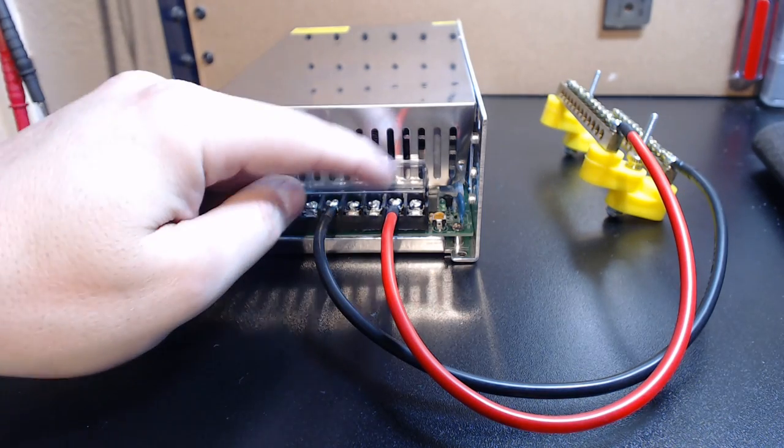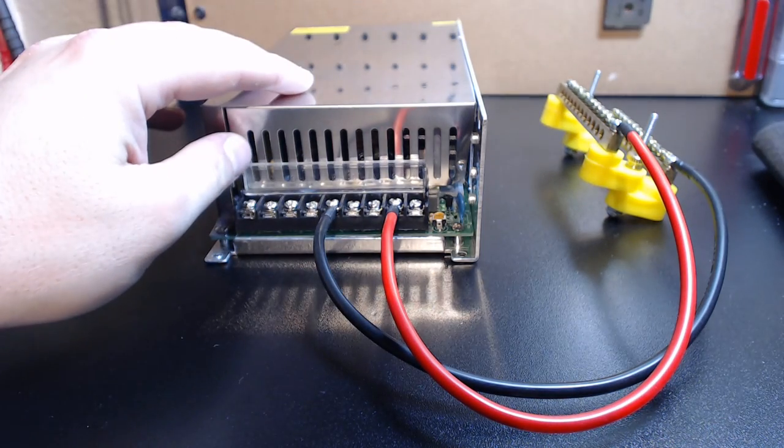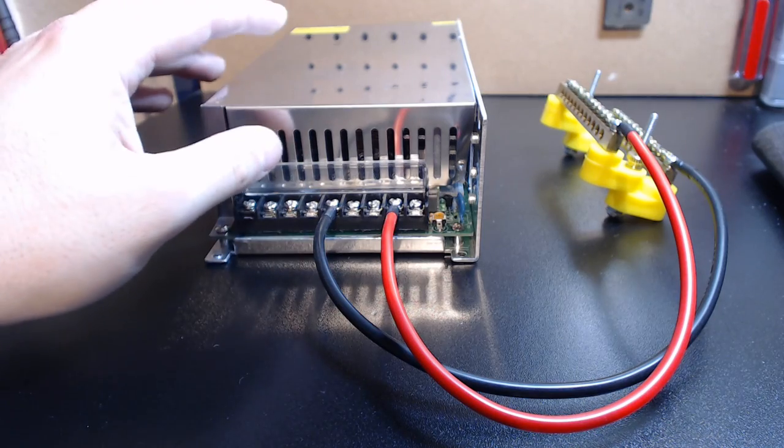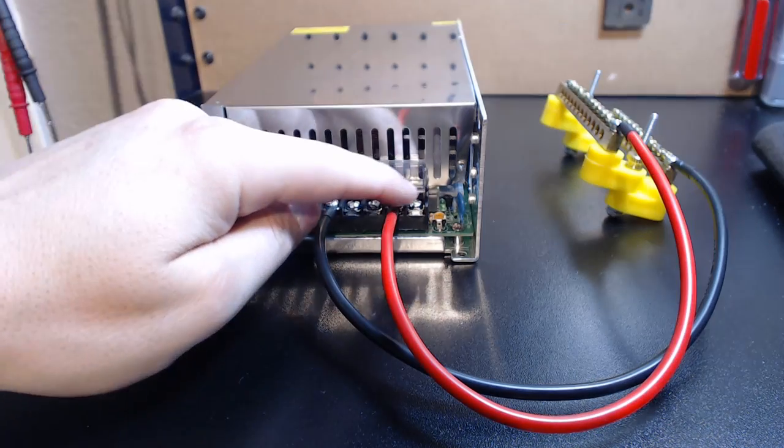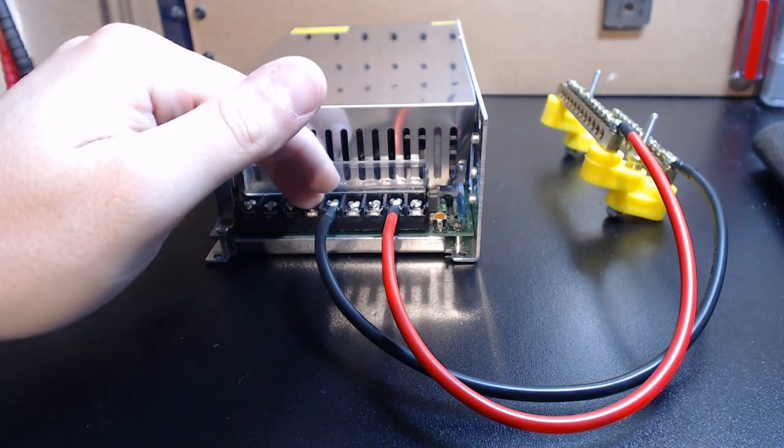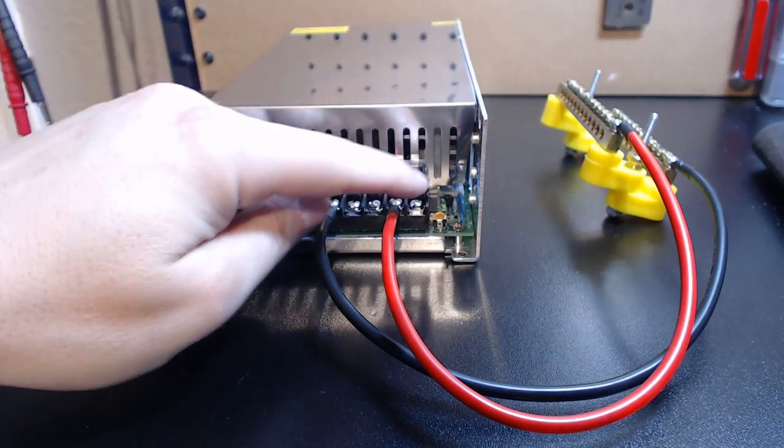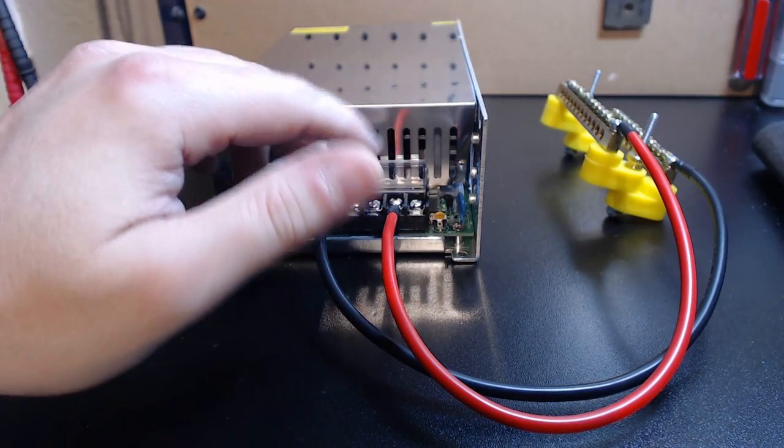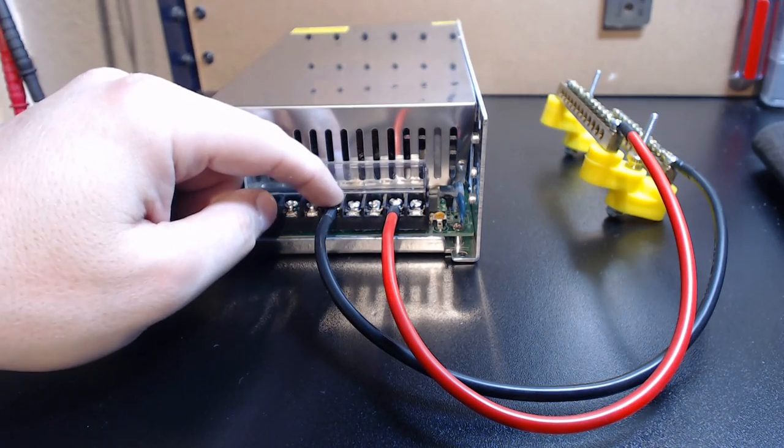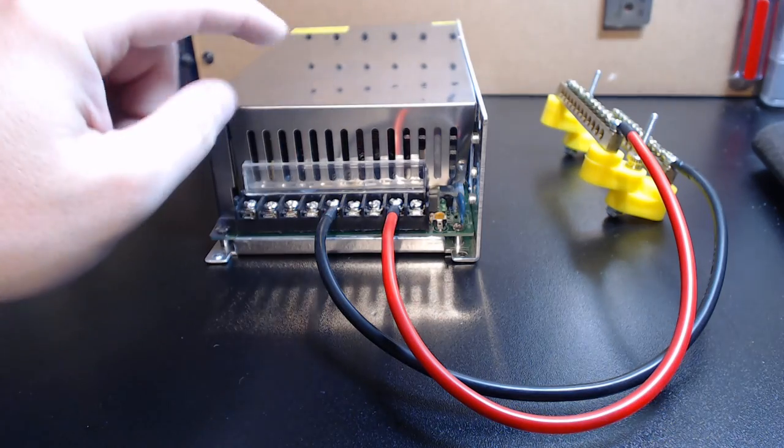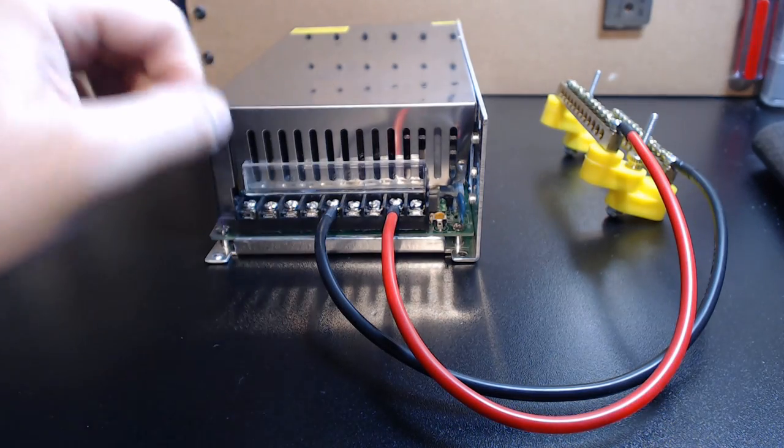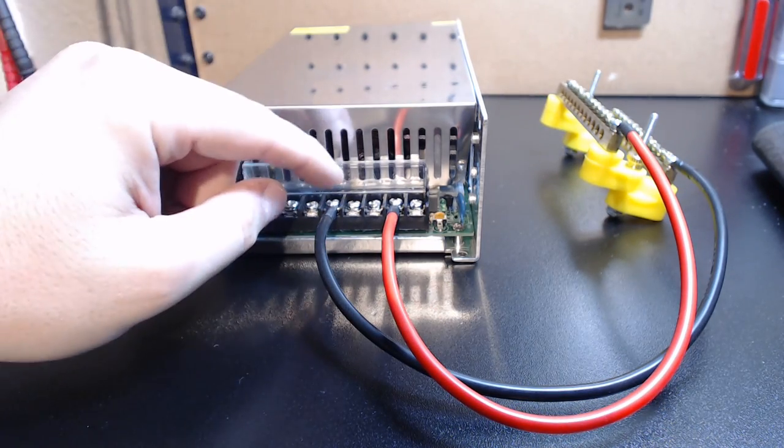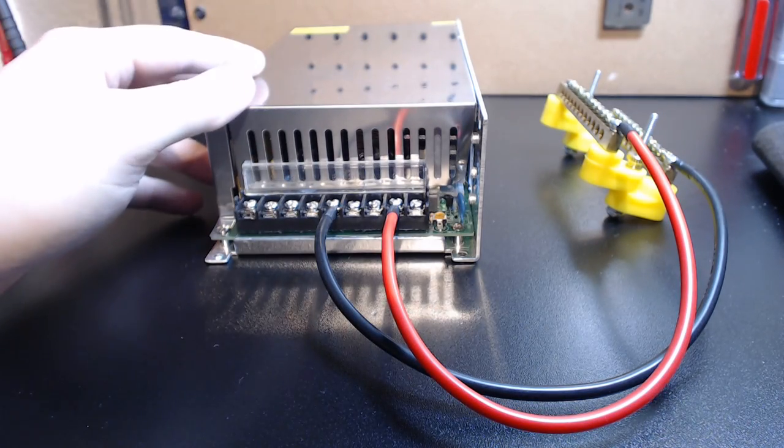Using this method allows for you to service your unit instantly. So instead of you, per se, mounting your power supply, running all your drives and sub-accessories to the bar itself, power supply fails, you've got to not only remove the power supply, but now you have to rewire all of your drives and sub-accessories. In this instance, let's say that same thing happens. All you would have to do is demount your power supply, remove the two terminals, pull the power supply out, put the new one in, put the two terminals back on, mount the power supply, and you're done.